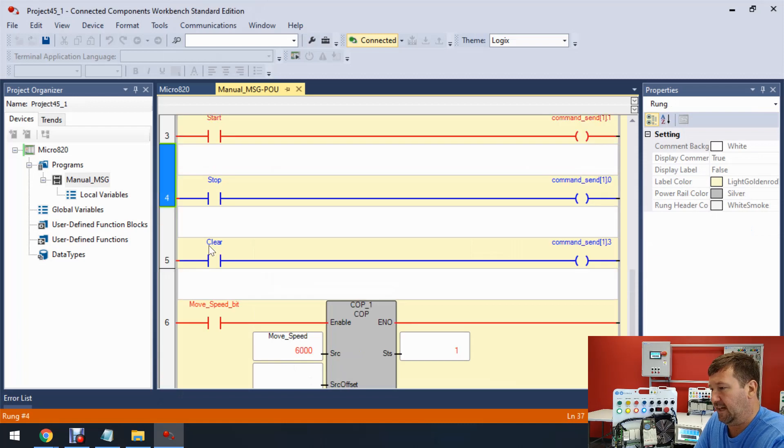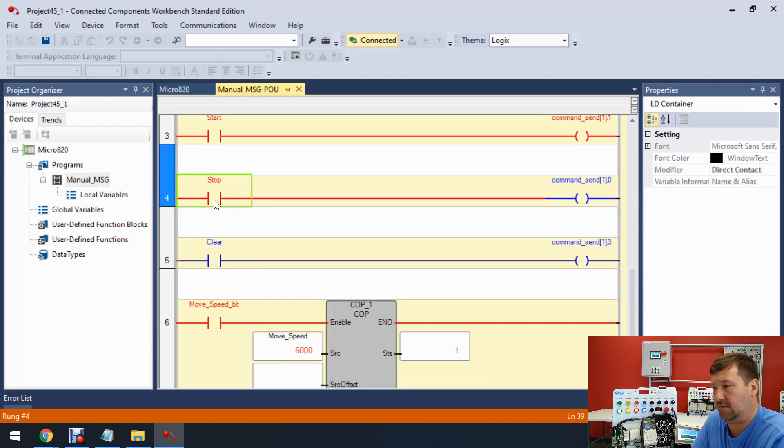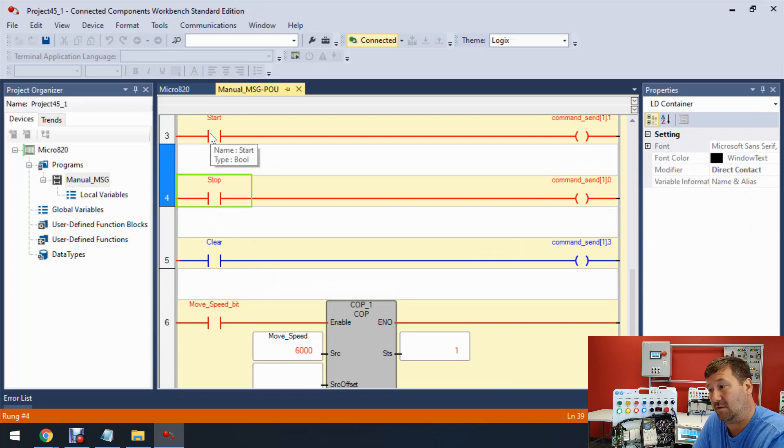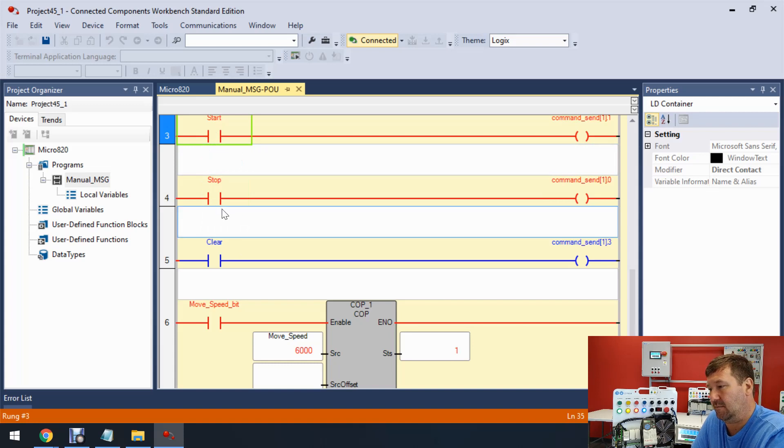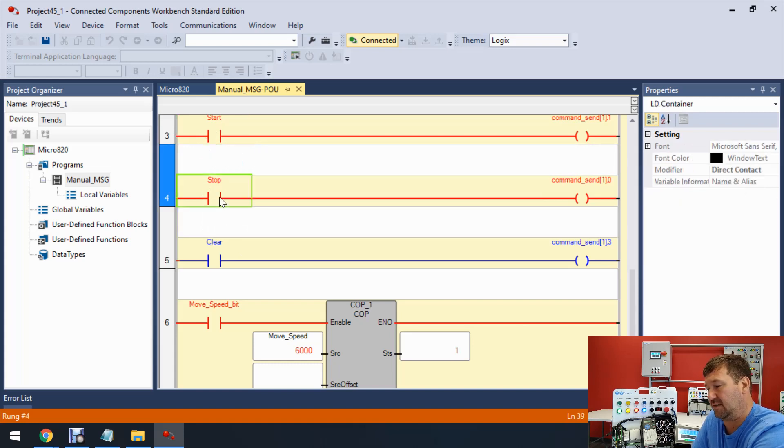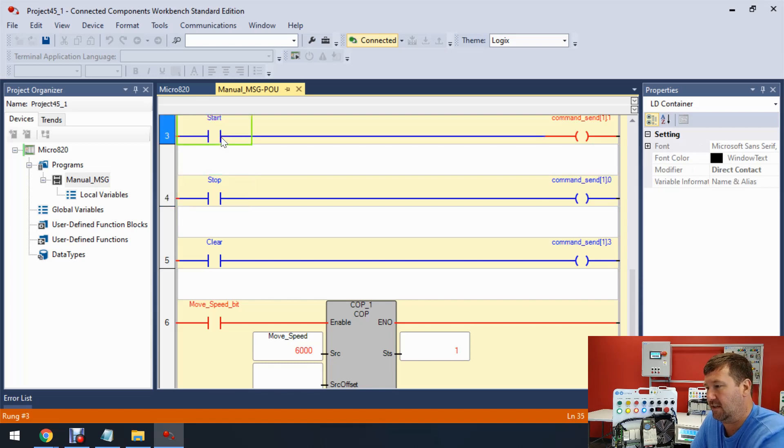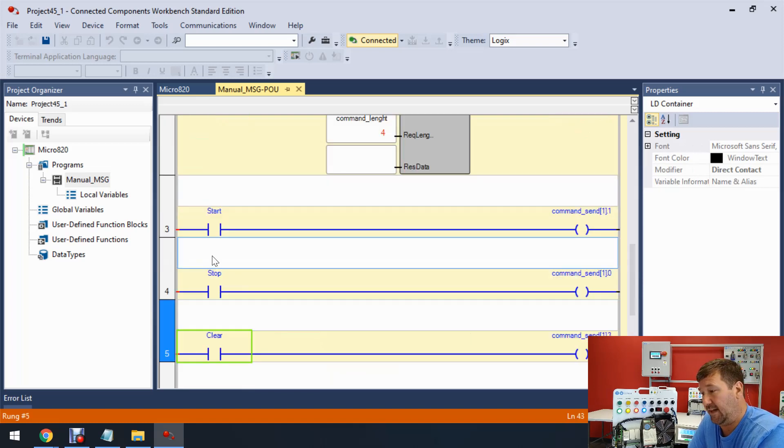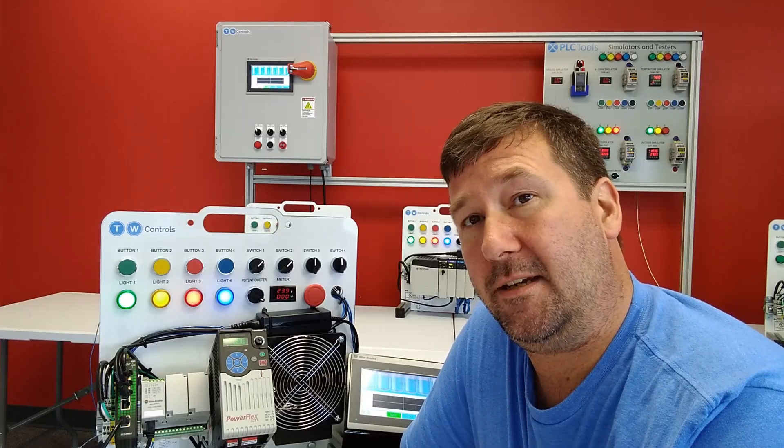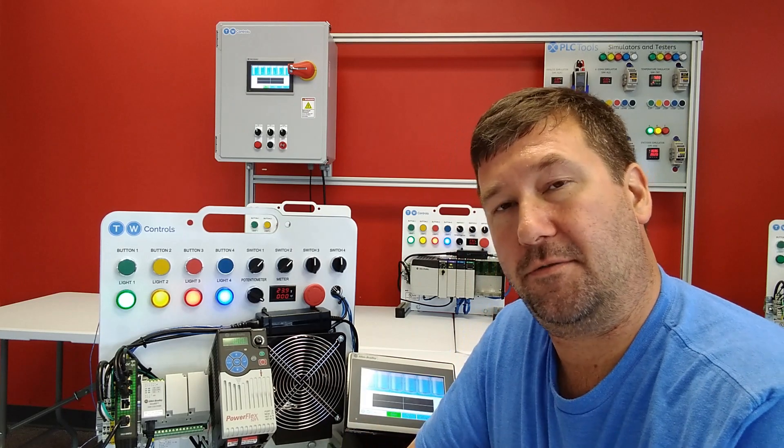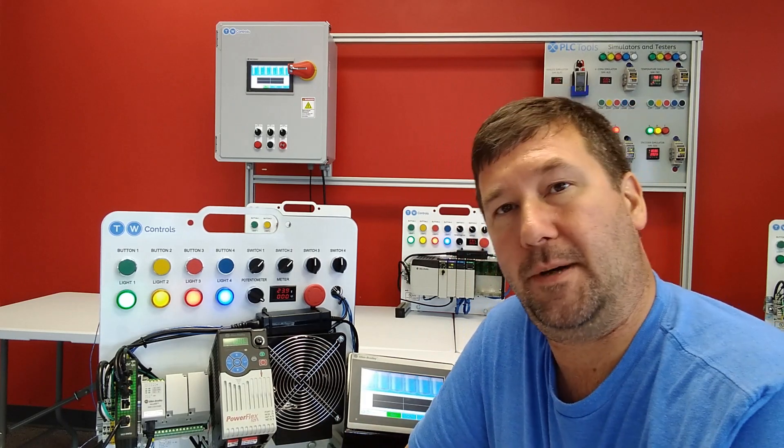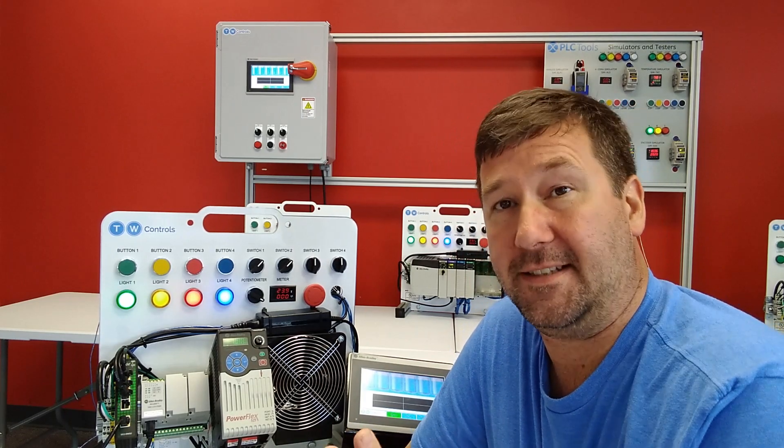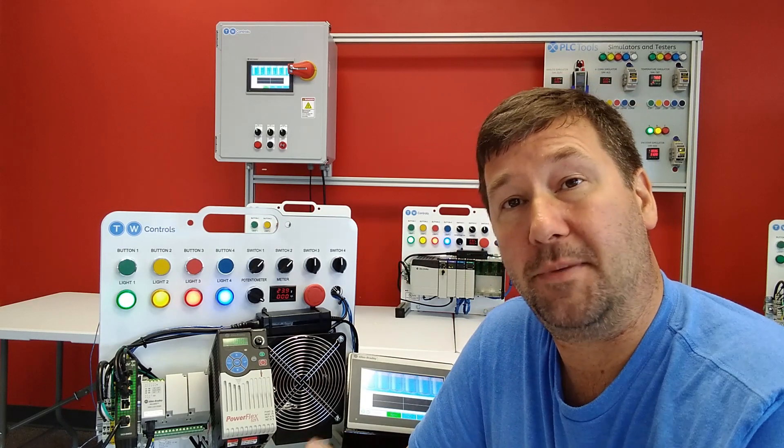And if we go back here, we can stop our drive. In fact, we don't even have to toggle the start off to make the stop work. It'll work at any time. But if we were to untoggle the stop, it won't immediately start back. You're going to have to toggle the start bit again. Now it also has a clear bit down here. And at first it won't appear it does anything. And here's why the really the user defined function block works better. But I think this is important to know how it works, because you may run into this out in the field.